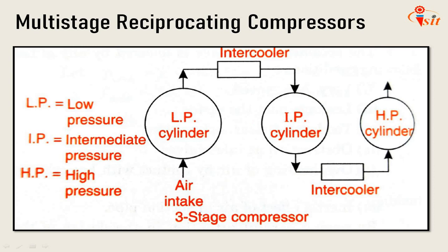The low pressure ratio in the low pressure cylinder means the clearance air expansion is reduced, since the effective swept volume of the cylinder is increased. Since it is this cylinder which controls the mass flow through the machine, because it is this cylinder which introduces the air into the machine, there is a greater mass flow through the multi-stage arrangement than the single stage arrangement.